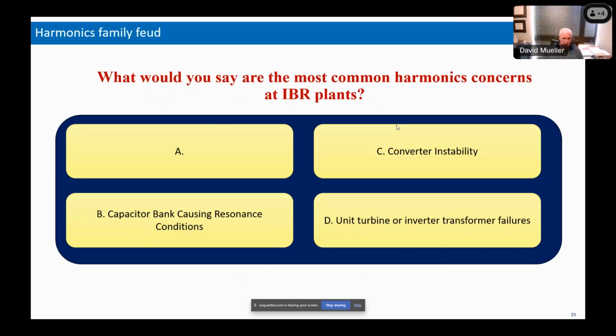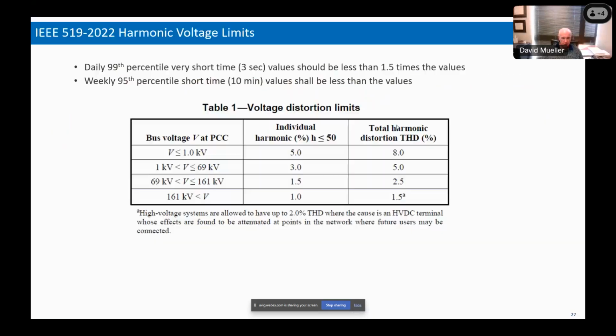One last one that I will highlight is when the background harmonic voltage distortion level is already over the limits. It's a pre-existing condition. It's not necessarily a problem. The grid's been living with that for years. Nobody's been complaining about it until we said, oh, we're going to go out and do a harmonic measurement at the plant. And oh, by the way, what we're seeing is that if we're a 230 kV system or a 345 kV system, our limit is 1.5% for the THD, and our limit is a minuscule 1% for an individual harmonic voltage distortion. In Europe, typical voltage limits for this type of thing in the IEC are 3 or 4% for high voltage systems.